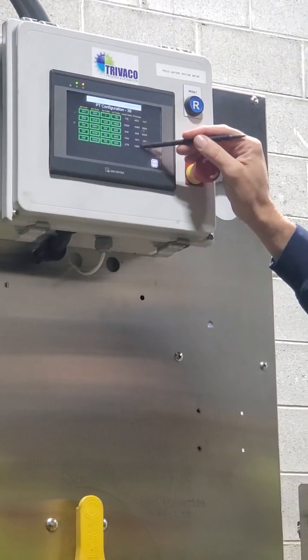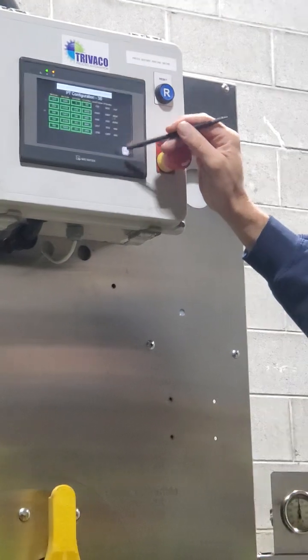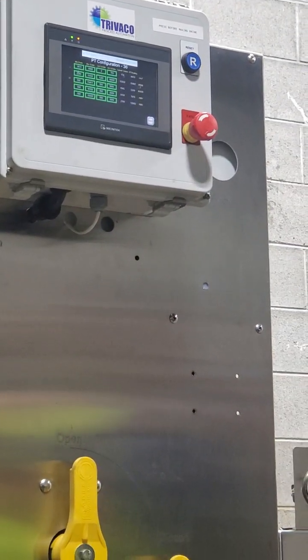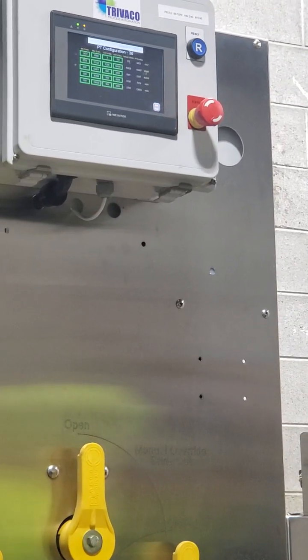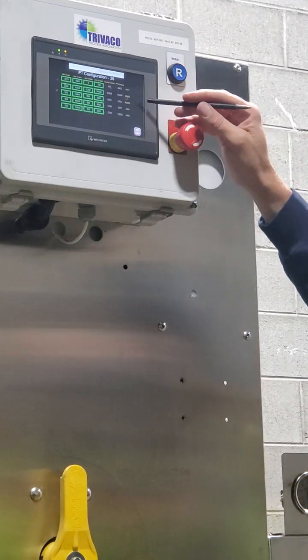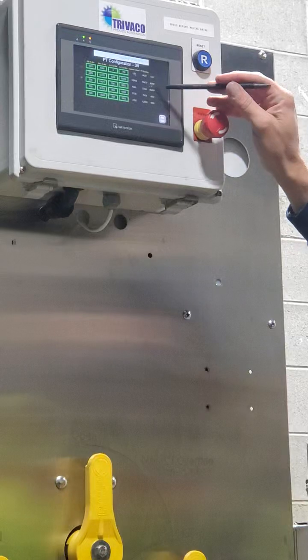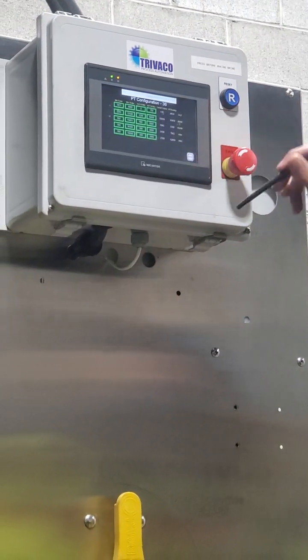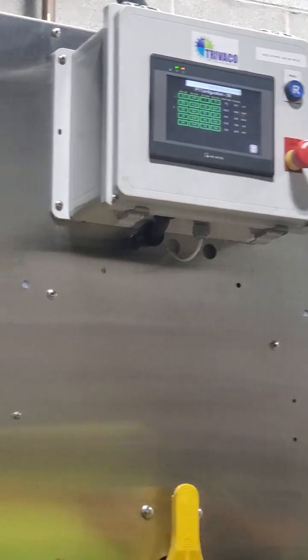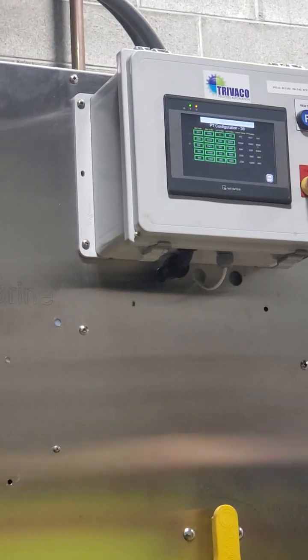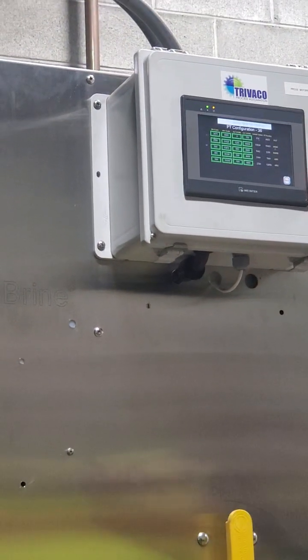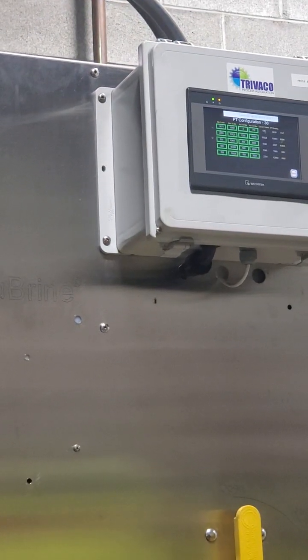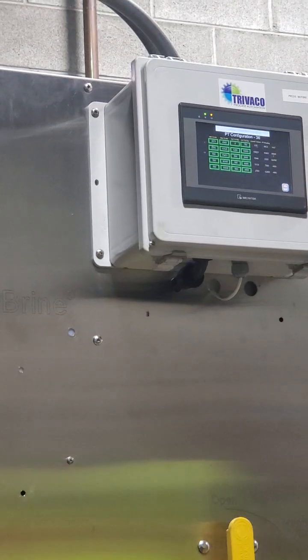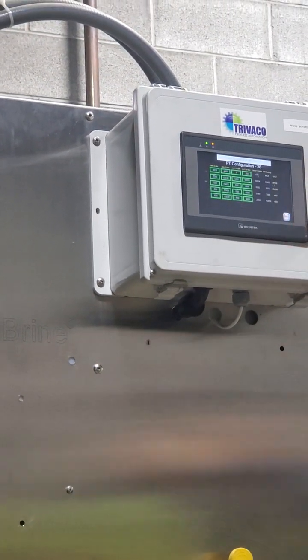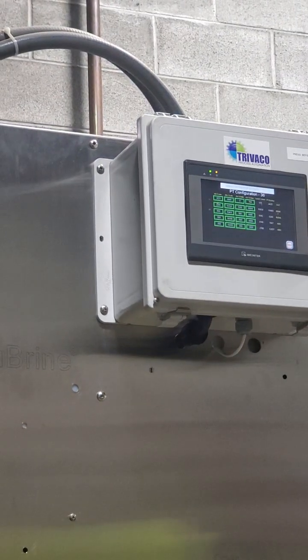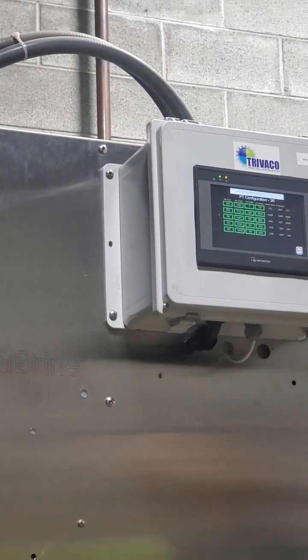The best way to check these three to see if there's a leak is to pull the tube out, out of the water, then slide it back down in there and reconnect the connector. If it's a slow leak, it'll give you a reading, but just let it sit there for 4 hours, then come back and take a look at that PT reading. If it's gone down, then you know it's a leak. If you recharge the tube, come back here and reconnect everything and it's still 0, then obviously it's a problem with the wire or the transducer. So the way to check these is to pull them all the way out of the liquid. Obviously, if you pull that tube out and you hear a lot of water drain out of it, there's a pretty good chance you have a leak. If you pull it out and nothing comes out of it, it's probably your transducer.